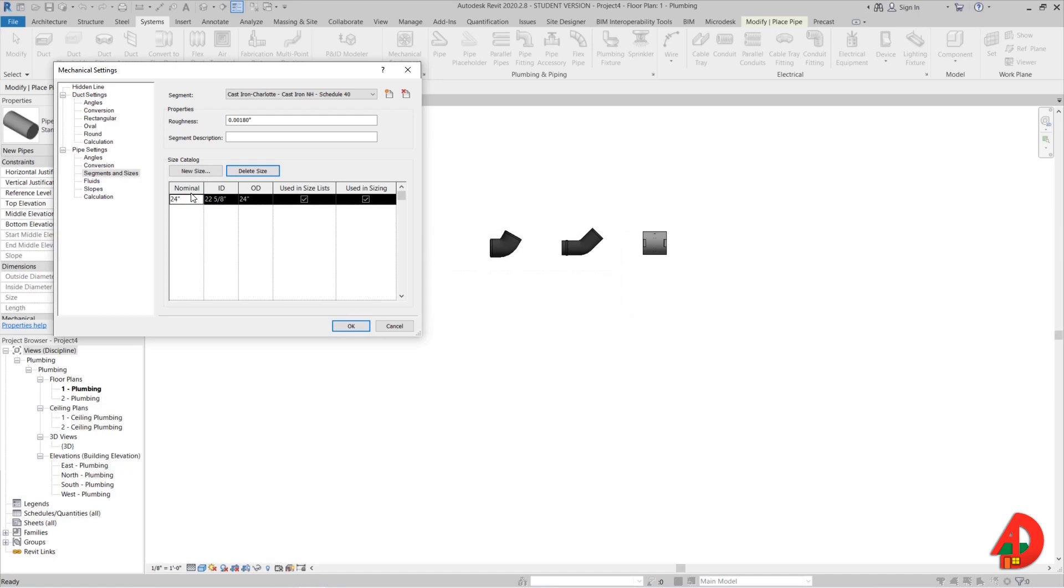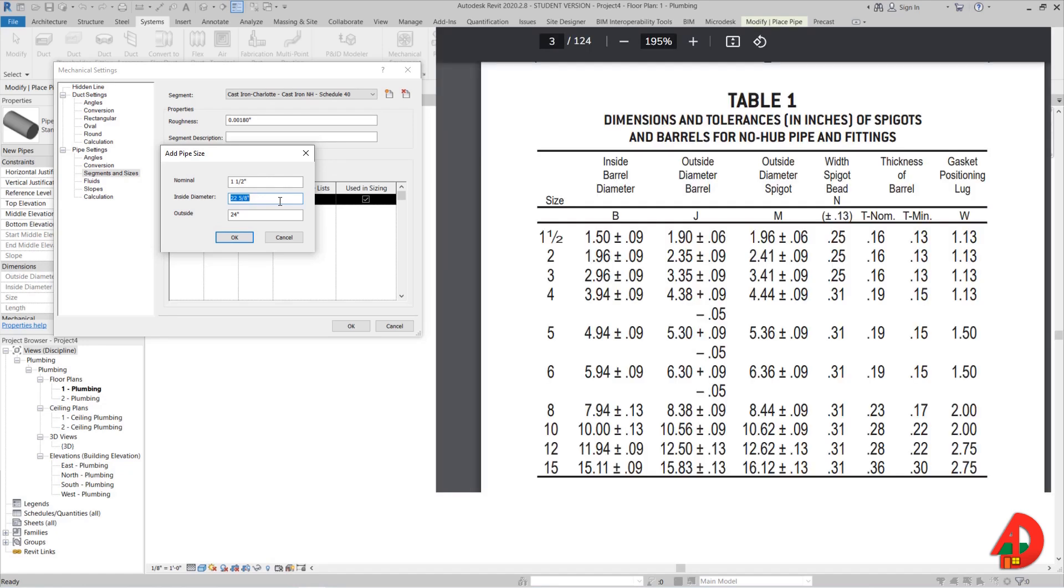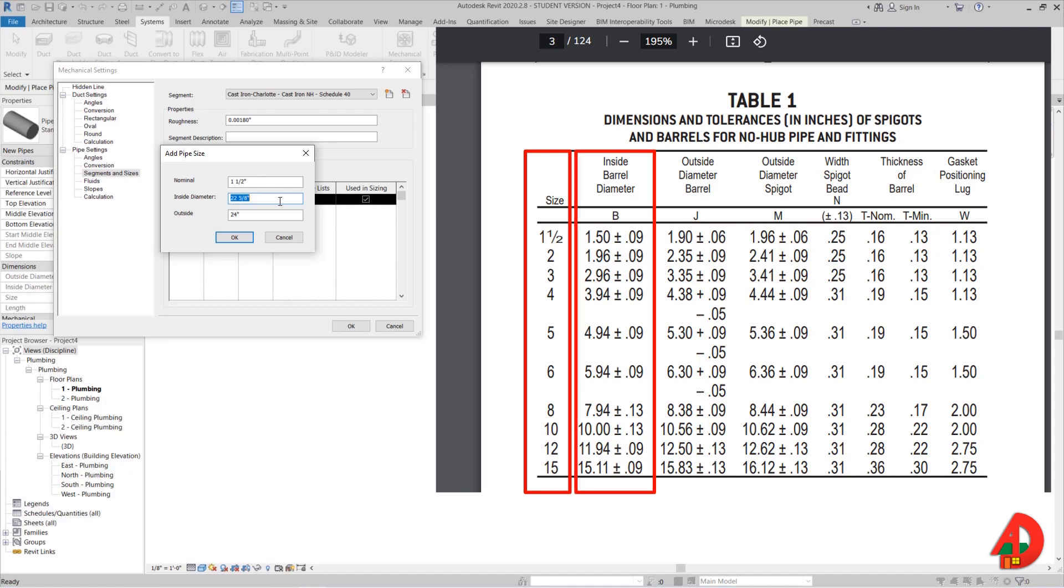I will close for now and pull the dimensions for cast iron pipes from a PDF file that you can download from the link below. The PDF is from the manufacturer website. I will add a new size, and from the table I can see the available sizes. I will start with 1.5 inches and also add inside diameter which is 1.5 inches and outside diameter which is 1.9 inches.